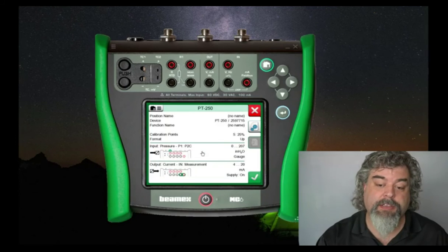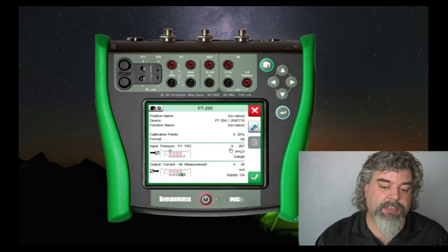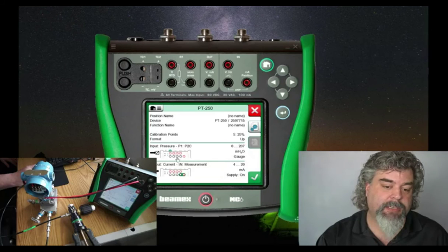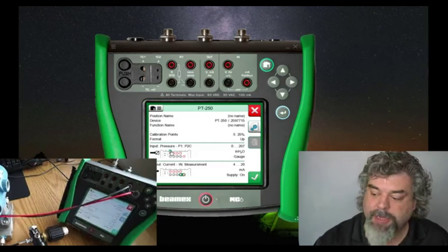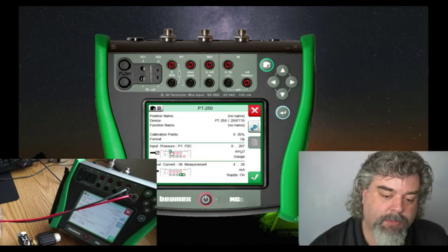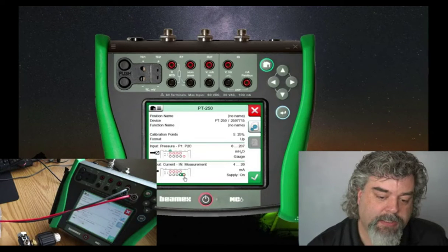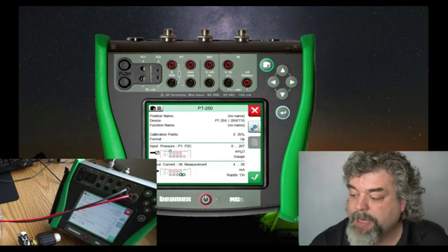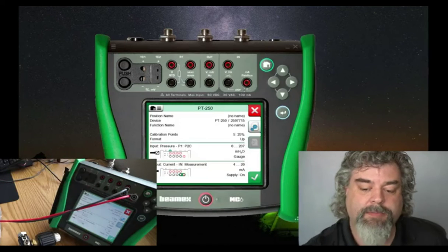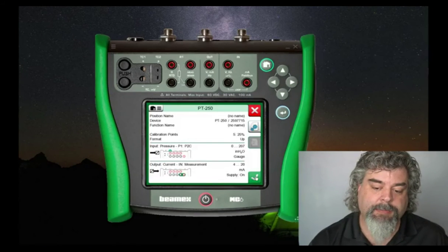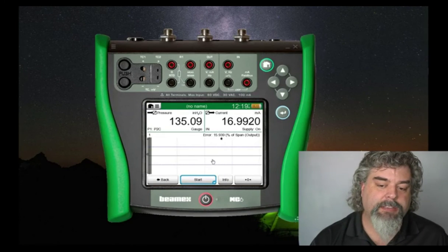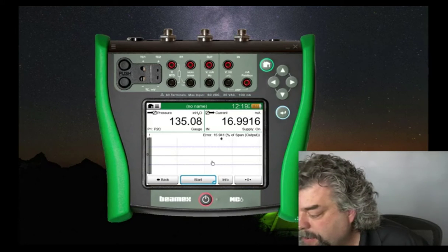Well, number one, if this is a 0 to 207 inch of water transmitter, that means at 0 we have 4 milliamps, and at 207 we have 20 milliamps. So we're connecting here, which is correct. I've got that over here. And then we're also connecting right here, which is these 2 guys, and I'm connected there as well. Loop power is on. I'm going to hit the check mark, and I have some pressure applied right now.